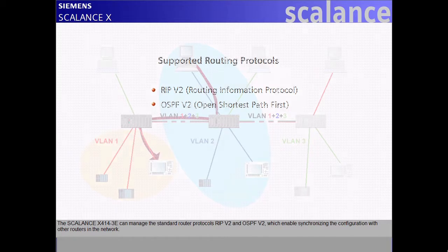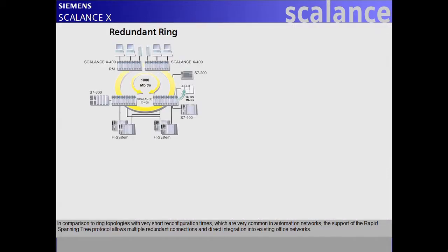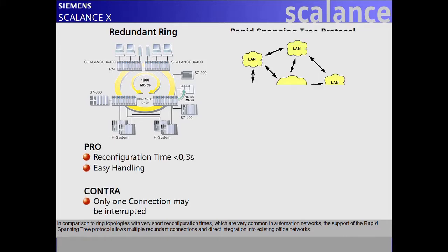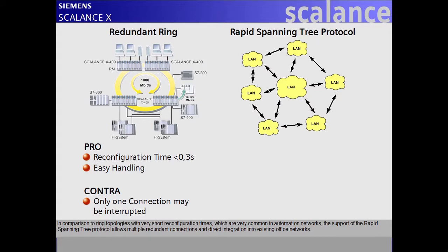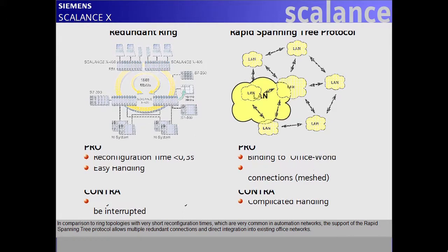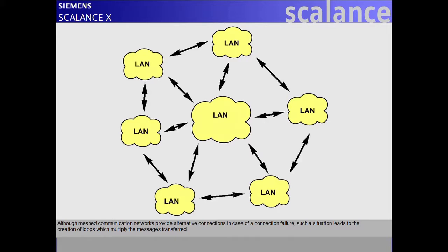In comparison to ring topologies with very short reconfiguration times, which are very common in automation networks, the support of the Rapid Spanning Tree protocol allows multiple redundant connections and direct integration into existing office networks. Although meshed communication networks provide alternative connections in case of a connection failure, such a situation leads to the creation of loops which multiply the messages transferred.